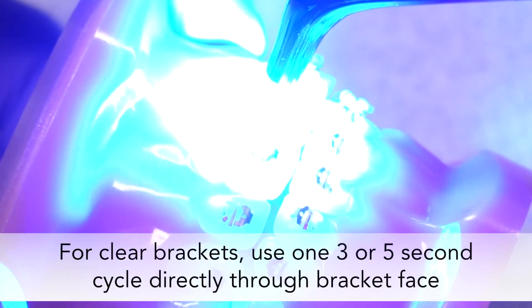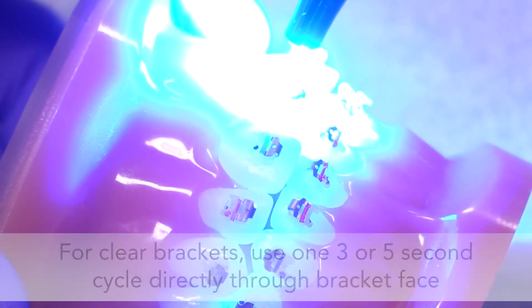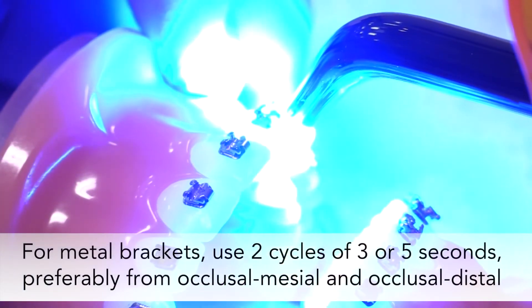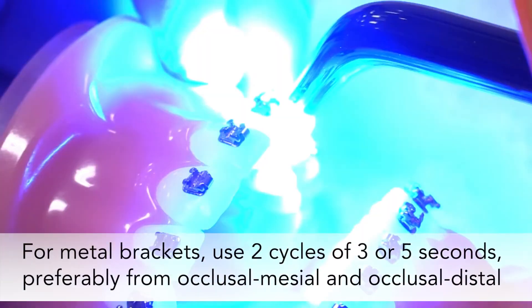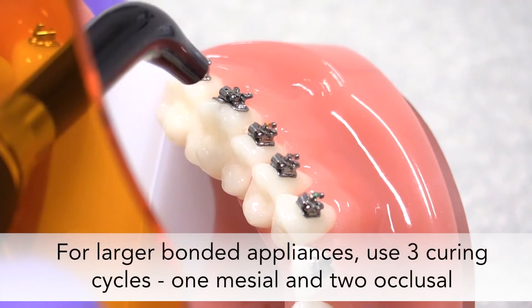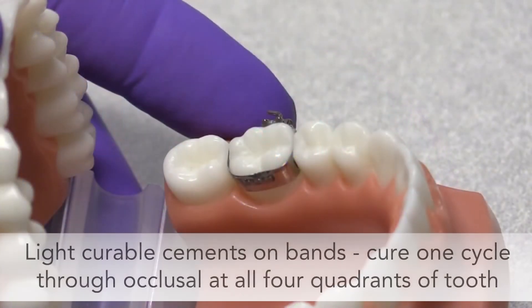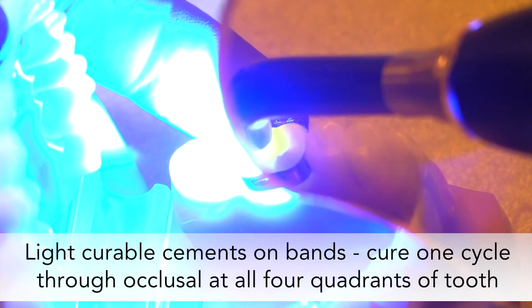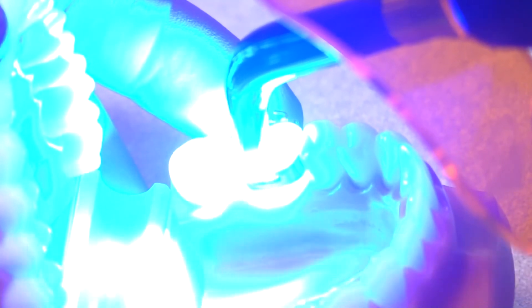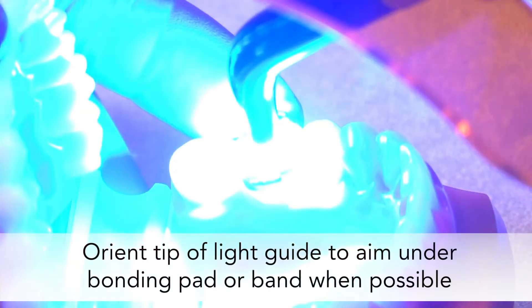When curing clear brackets, we recommend one curing cycle of 3 or 5 seconds directly through the face of each bracket. For metal brackets, we recommend two cycles of 3 or 5 seconds each, preferably from occlusal mesial and occlusal distal. With larger bonded appliances like direct bond tubes, we recommend three curing cycles — one mesial and two distal. For light-curable cements on bands, cure one cycle each through the occlusal at all four quadrants of the tooth. Always orient the tip of the light guide under the bonding pad or band whenever possible.